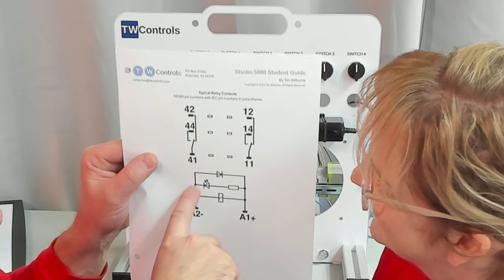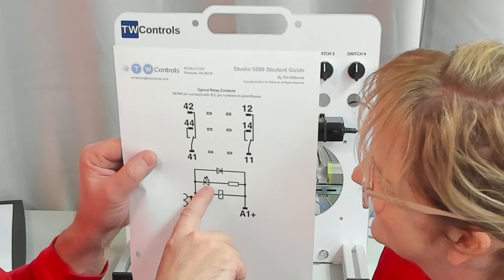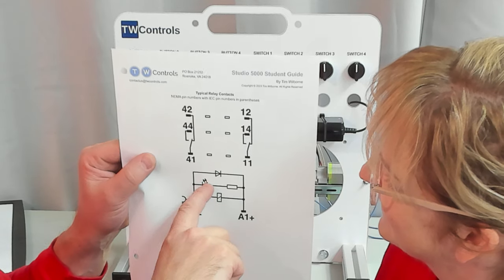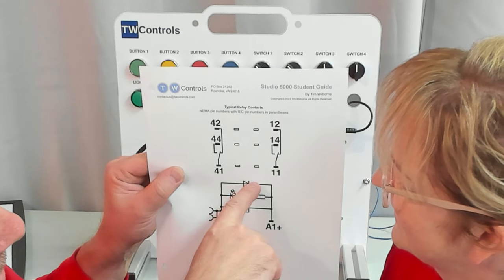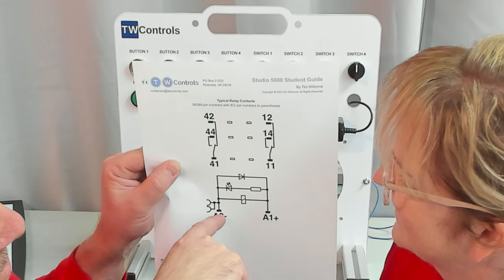But when you start seeing these symbols right here, these are diodes. This diode right here is not going to let current through to get to A2, and so it has to go through its normal circuit, which includes energizing that coil.